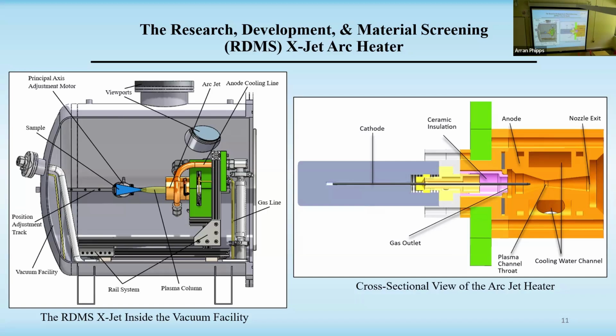So yeah, here's the plasma column, gas line. So everything just coming through here. And here's a cross-sectional view. So we have our thoriated tungsten cathode. Insulation. So we have to insulate properly so there's not unwanted arcing. So we insulate the cathode. And then here's our copper anode. This is the key component that needs to be cooled or it'll be obliterated quite quickly. So we have a channel here, high flow rate of cooling.